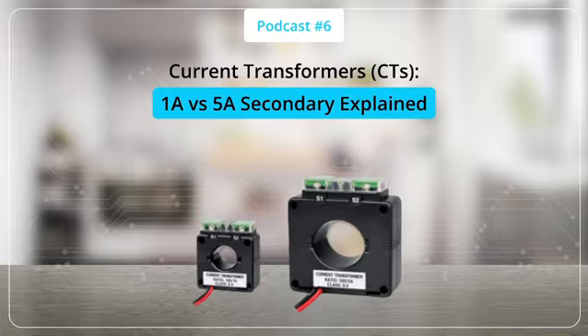This is explained by the principle where losses increase with the square of the current. For example, in a 5A system, higher current flowing through long cables leads to increased heat and voltage drops. This reduces accuracy, especially over long distances. Because of this, 1A CTs are often preferred in modern systems where long cable runs are involved.